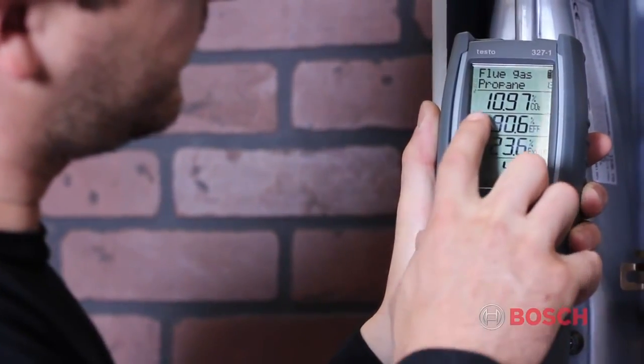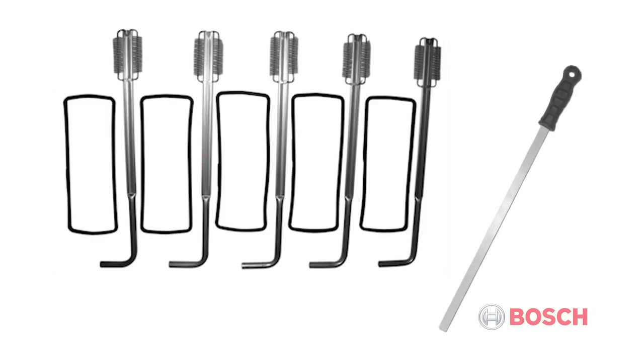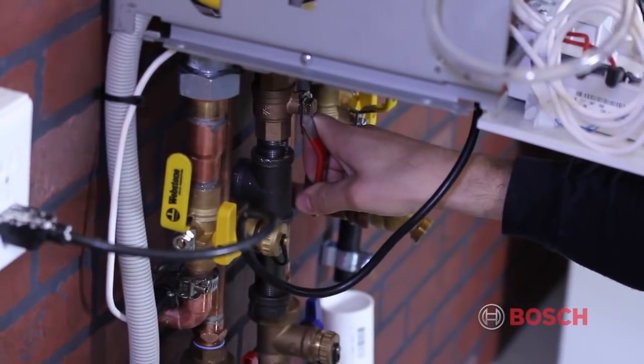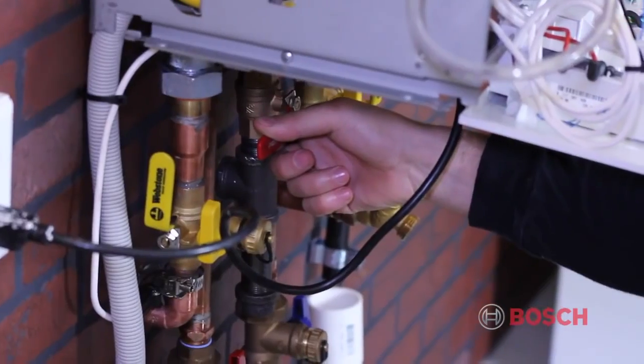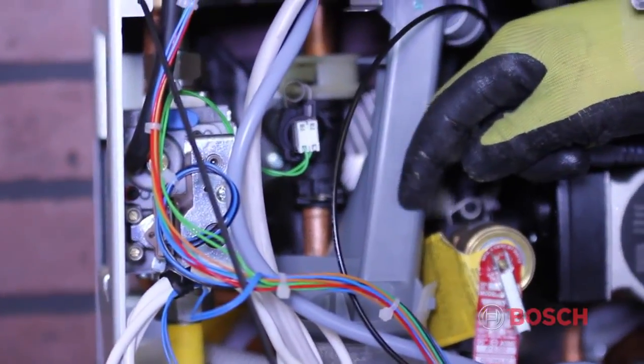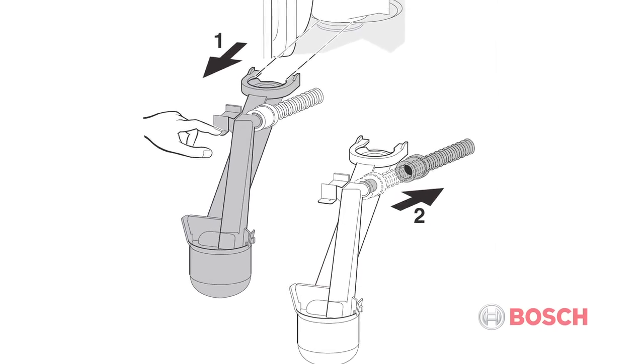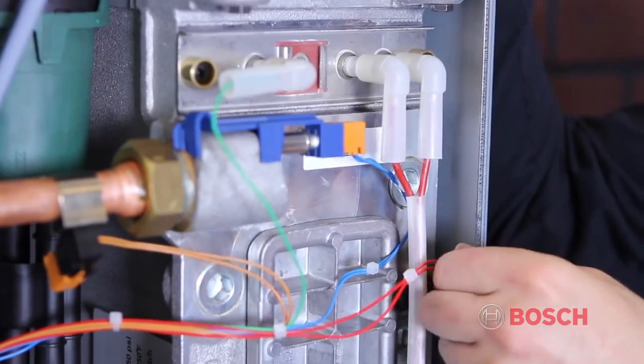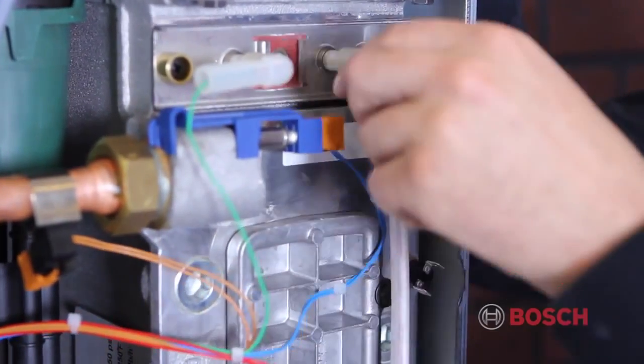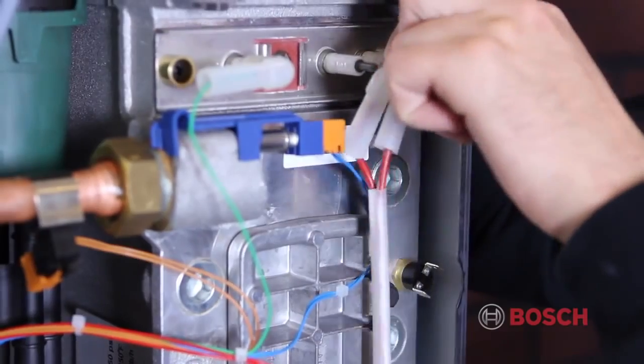If mechanical cleaning is required, Bosch offers the Service Accessory Kit, which includes main heat exchanger gaskets, a heat exchanger brush, and a heat exchanger cleaning blade. In order to prepare for inspection of the heat exchanger, shut off the electricity and the gas. Remove the condensate trap and place a suitable container underneath. Remove the wires from the high limit primary sensor, spark igniter, and flame sensor.